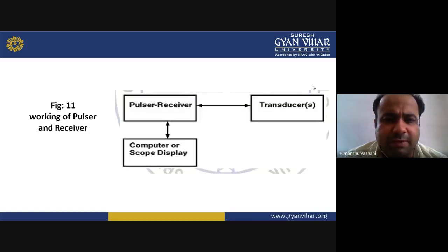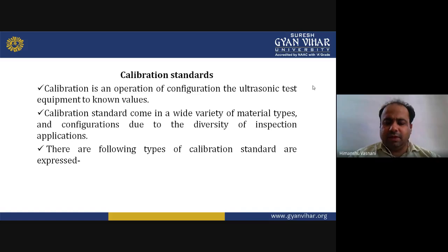That's again the same diagram that you can see. Now there are calibration controls. What is calibration? Calibration is important because you have to calibrate what you are getting. Calibration is an operation of configuring the ultrasonic test equipment to known values. The calibration standards come in a wide variety of material types and configurations due to the diversity of inspection applications.